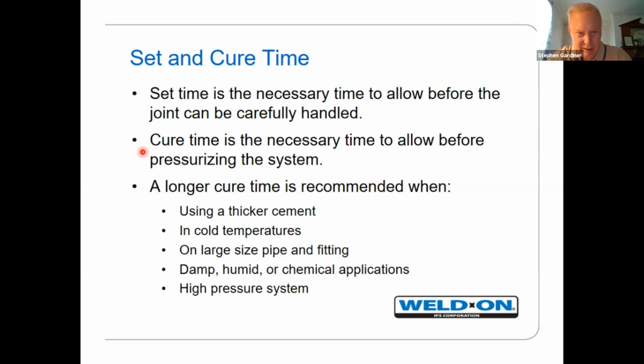Central part of the continent, okay? Colorado Springs, Colorado. A fab shop ran all their compressed air lines with PVC pipe. It failed over a weekend. Luckily, nobody was in the building. When they came Monday, they all stood out in the parking lot, staring at their building, trying to figure out what happened to the exterior wall of the building. That's where the compressed air lines were. The wall got taken out. So always use water, okay?